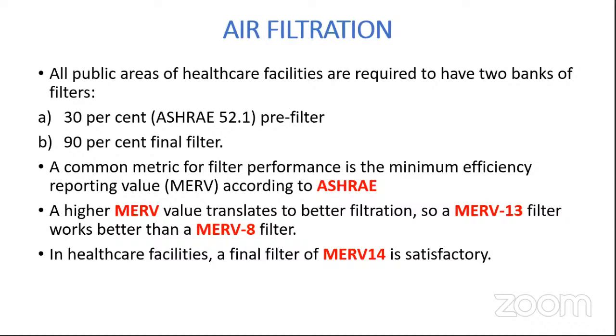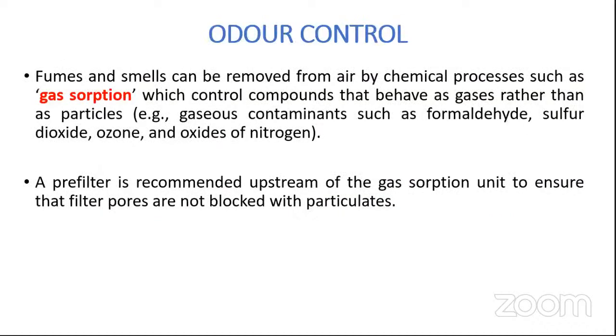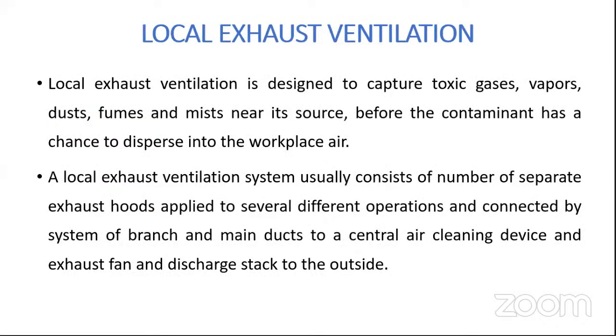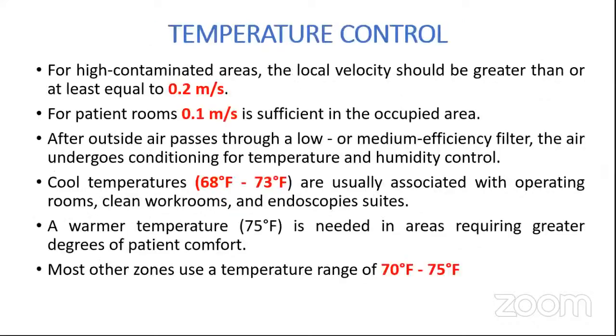When we talk about the MERV value, MERV is the minimum efficiency reporting value. According to ASHRAE, for healthcare it needs to be around 14. MERV 14 is said to be satisfactory for healthcare facilities. For odor control, gas absorption is the option for taking care of the gaseous components besides the particles. The filtration takes care of the particulate. Now, for local exhaust ventilation, we need to make sure that there are a number of separate exhaust hoods which give away the exhaust air outside, at least 4 meters above the place or 2 meters above the roof of the facility.